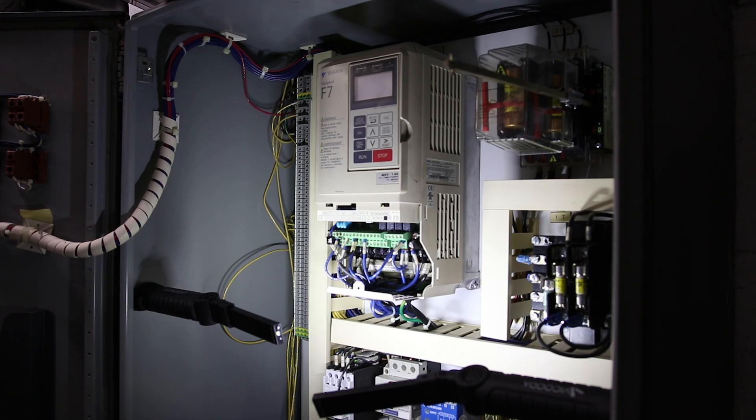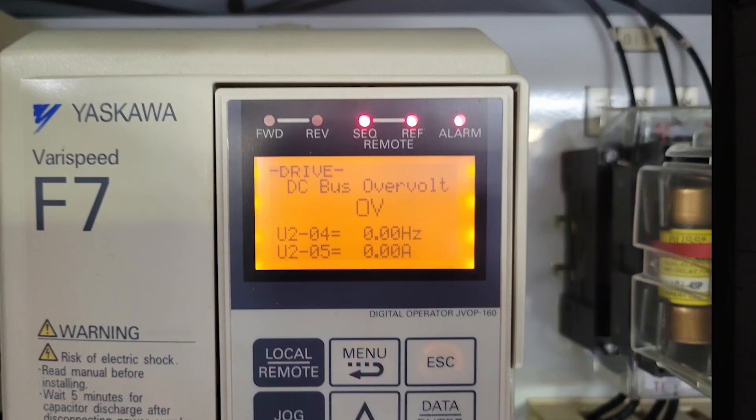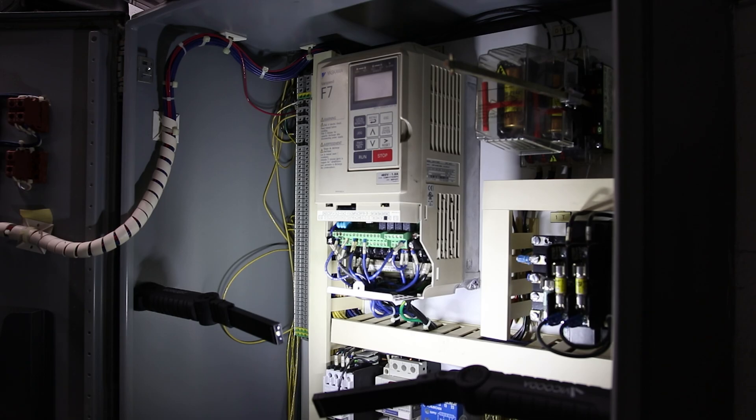Today we're replacing a Yaskawa Varispeed F7. The reason we're replacing this is because we had a DC bus overvoltage and now we cannot get the conveyor to run.